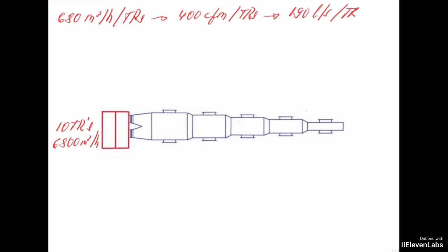It's not fixed. You can reduce this flow. You can increase the flow. Because in most central air conditioning equipment, the flow is adjustable. But basically, when we want to dehumidify the environment, we lower this standard flow. And when we want to attack too much sensible heat, we increase this flow.